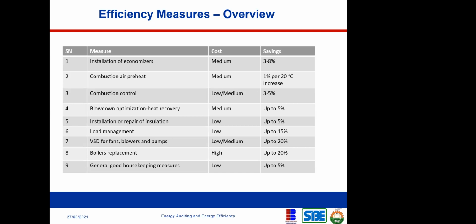You can do load management. Okay, you don't operate your boiler on part load. It's not hygienic. It's not efficient to do that. So the other one is to install VSD for fans and blowers and pumps. Now, when we are talking about a boiler, there are other components of the boiler system apart from the burners and the pipes that transport the steam and all of that. There are also fans, there are also blowers. Okay, so for those fans and blowers, you might need to install variable speed drive or variable frequency drive. They all mean the same thing, to be able to control them so that they can match the load on the boiler. Okay.